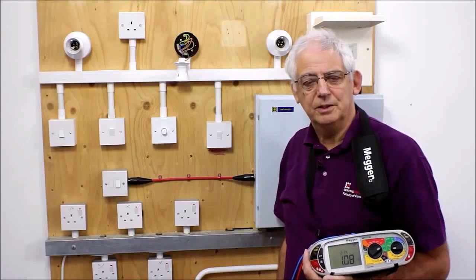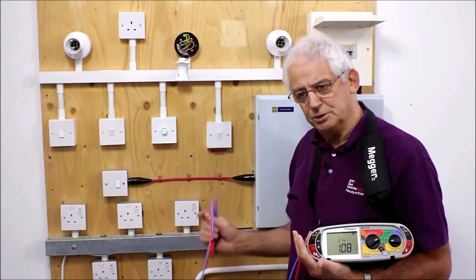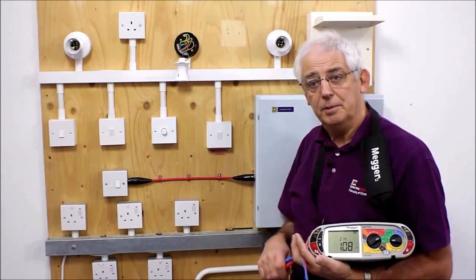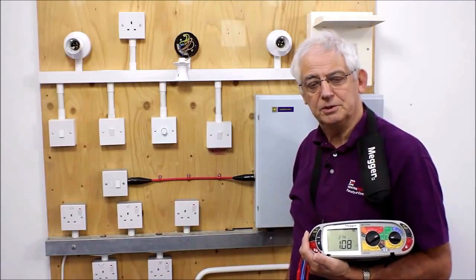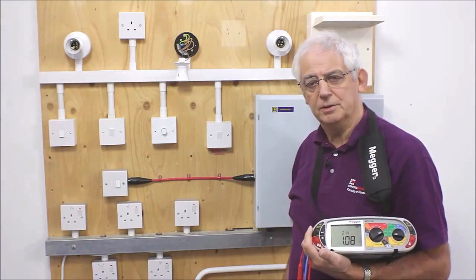Obviously, you need to do it at the furthest point. If you're not sure which is the furthest point, it may be that you need to do it at several points on the circuit, and the highest value that you measure is going to be recorded as your Zs.